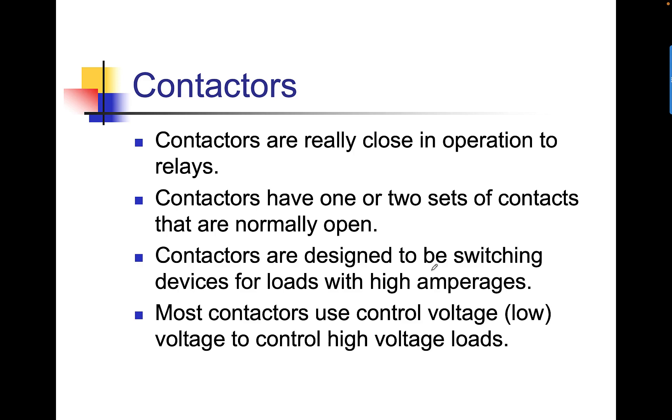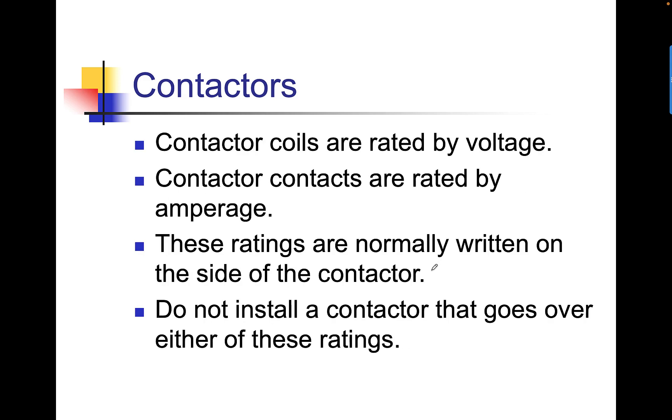Contactors are really close in operation to relays. A contactor has one or two sets of contacts that are normally open. Contactors are designed to be switching devices for loads with high amperages. Most contactors use control voltage to control high voltage loads. We use low voltage controls that control high voltage loads. Contactor coils are rated by voltage. Contactor contacts are rated by amperage. Sound familiar? It's the same as the relay. These ratings are normally written on the side of the contactor. Do not install a contactor that goes over either of these ratings.